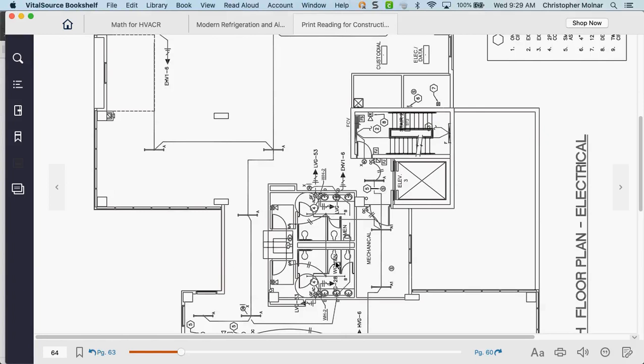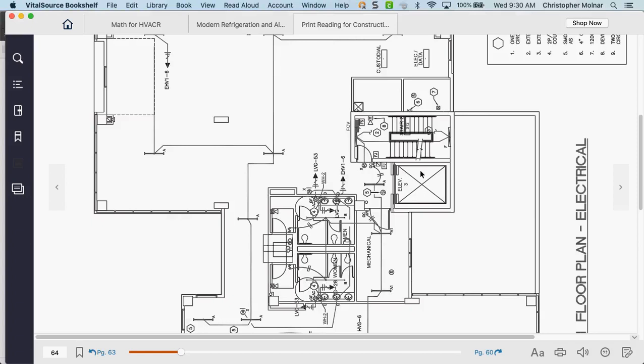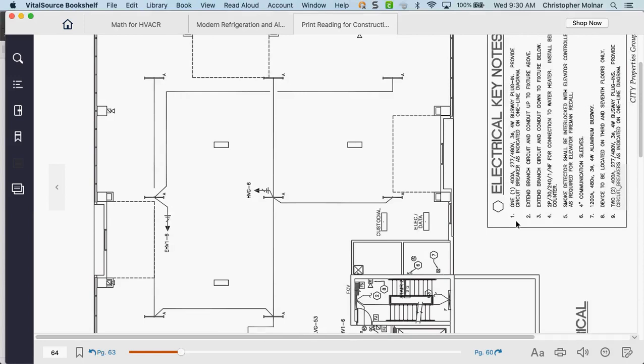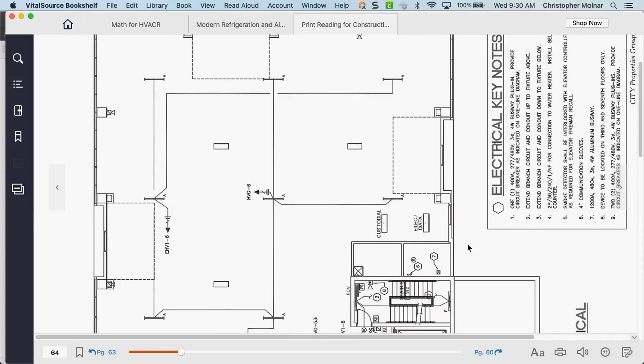Elevator shafts are extremely important. When you look at an elevator shaft, it might look like you have plenty of room around the outside, but according to code, we can't run any wiring or duct work in an elevator shaft — not allowed to, even if you could fit it next to the elevator. Elevator shafts are protected fire zones in commercial buildings. There are also electrical keynotes that tell you exactly what needs to be done. You're not going to run wiring or duct work where their lights and electrical are — can't do it.